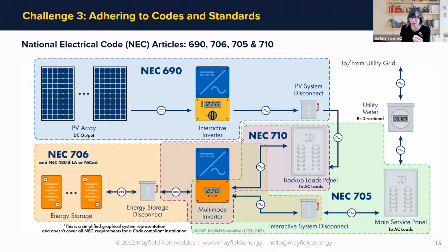But where those sources come together is covered by 705, interconnected power production sources. So you've got to go to 705 for those rules. And then if you operate in standalone mode, which is like all of a sudden you're off grid because the grid went down, you can apply the rules of 710. Although some AHJs may actually require you to apply 702.